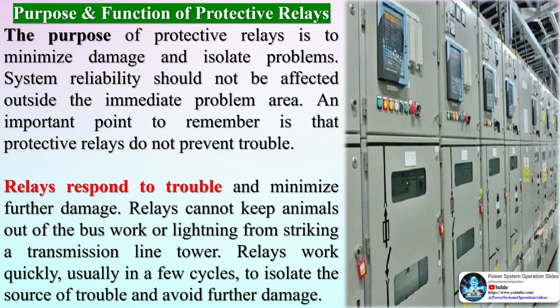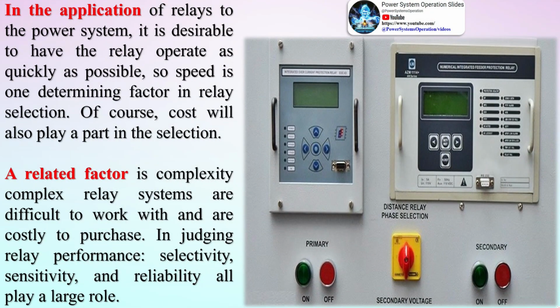The purpose of protective relays is to minimize damage and isolate problems. System reliability should not be affected outside the immediate problem area. An important point to remember is that protective relays do not prevent trouble. Relays respond to trouble and minimize further damage. Relays cannot keep animals out of the buswork or lightning from striking a transmission line tower. Relays work quickly, usually in a few cycles, to isolate the source of trouble and avoid further damage.